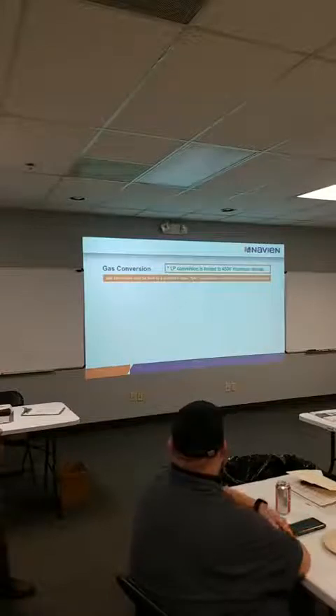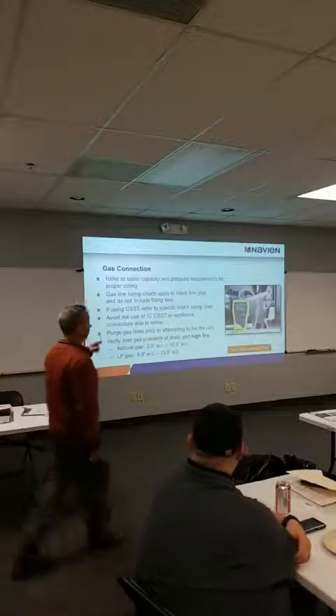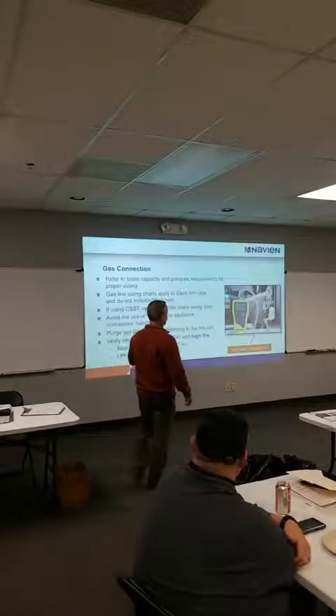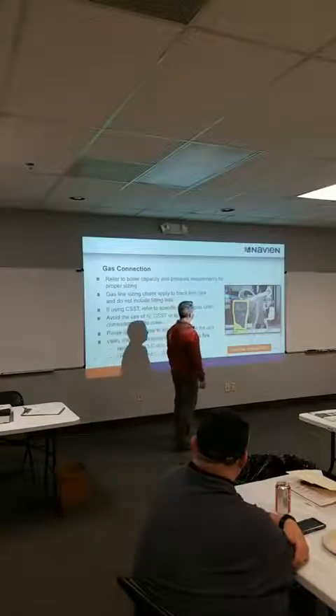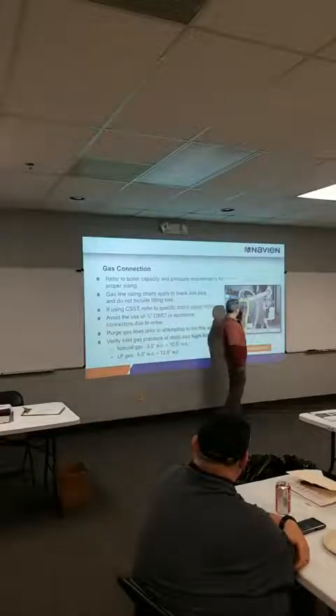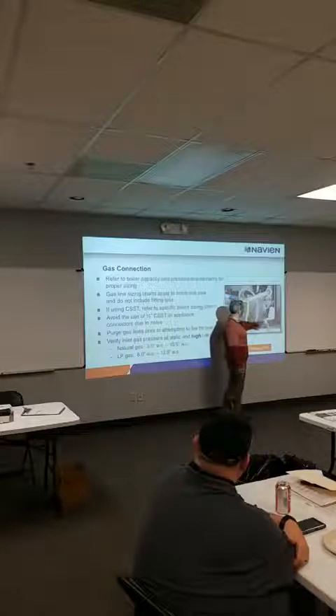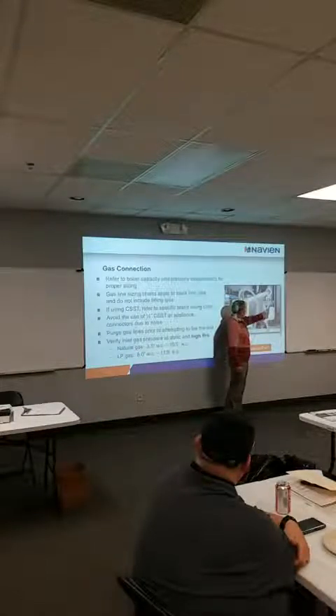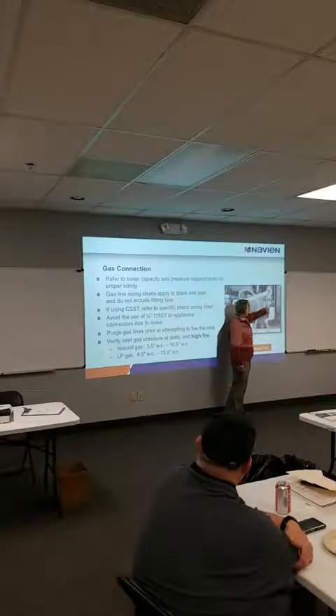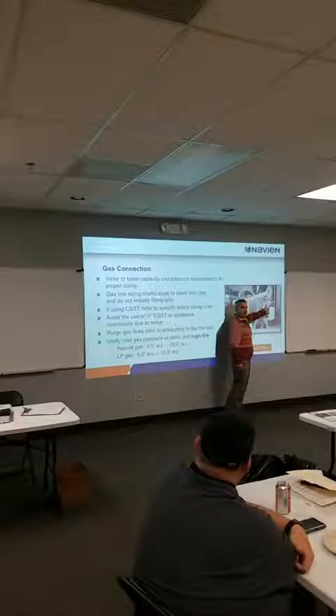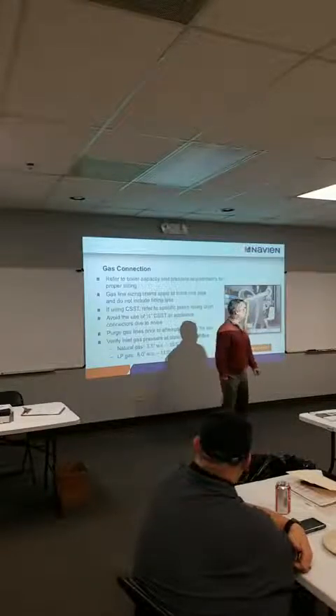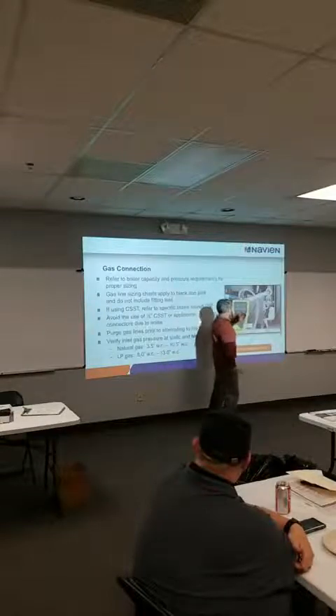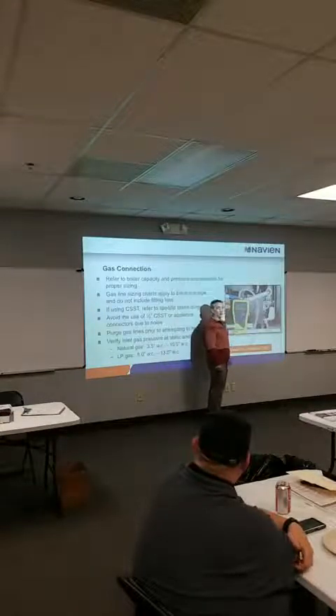All of our gas valves are gonna look very similar, except for again on the commercial boiler, it's a little different, but not much. You can use a single port or dual port digital manometer. The lower adjustment is your static pressure. There's a port above that for our air to gas ratio testing. And your air to gas ratio adjustment is right here under this little cap. There's a little Allen head, take the cap off, little Allen head adjustment underneath of it. We drop this thing into min fire when we do our air to gas ratio testing.